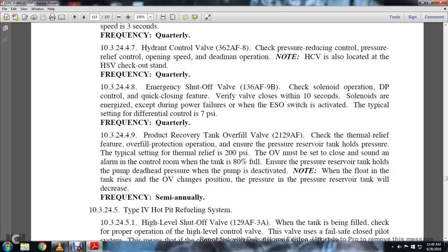Product recovery tank overfill: check the thermal relief and overfill protection operation. Ensure the pressure reserve tank holds the pressure. The typical setting for thermal relief is 200 psi. The overfill valve must be set to close and sound an alarm in the control room when the tank is 80% full. Ensure the pressure reserve tank holds the pump deadhead pressure when the pump is deactivated. Note when the float in the tank rises and the overfill valve changes position, the pressure in the reserve tank will decrease. The inspection for the product recovery tank overfill valve is semi-annually.